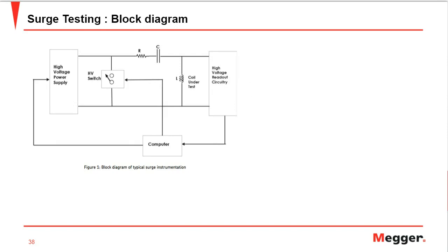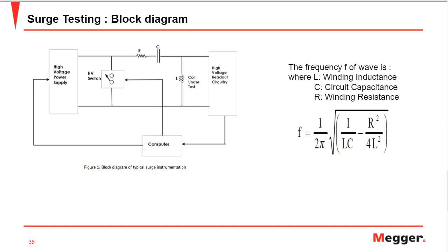And here's a block diagram of the circuitry that goes into surge testing. First of all, there's a high voltage power supply and a high voltage switch. The motor is represented as a coil or an inductor. Once the capacitor is charged on the high voltage power supply side, the switch sends pulses to the motor, and there's a frequency, also called the ringing frequency, which the software analyzes through its algorithm after measuring the pulses and the rise of the pulses, from one pulse to the next.